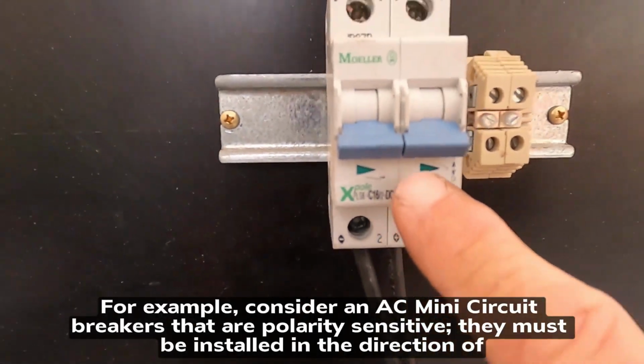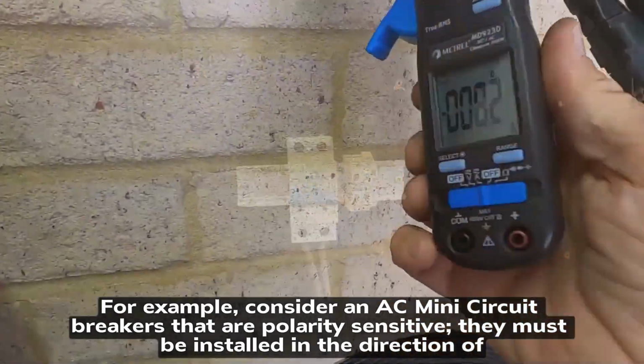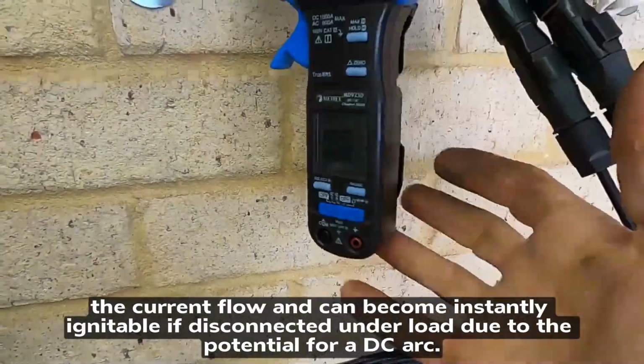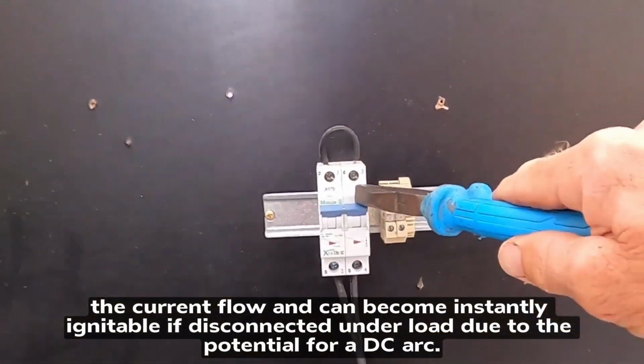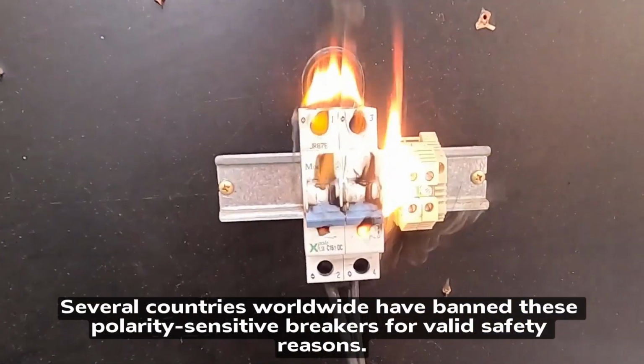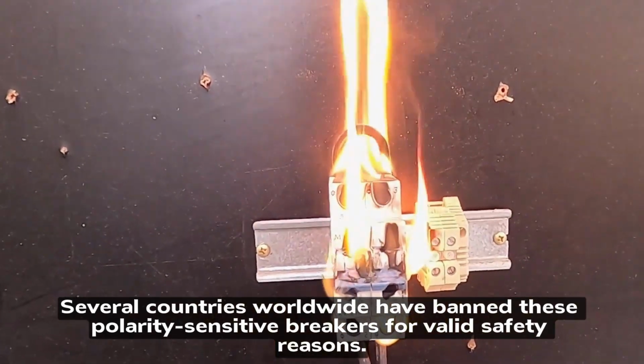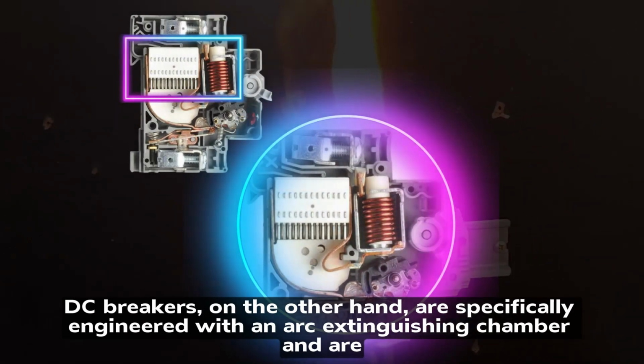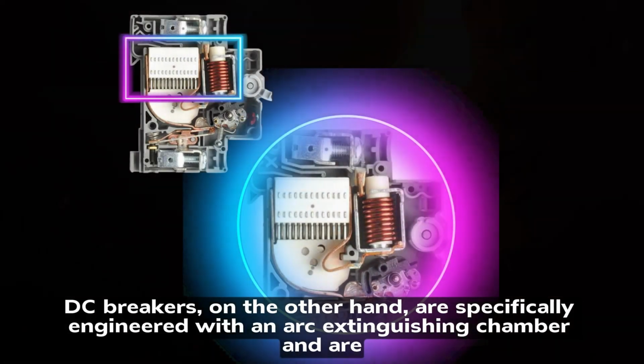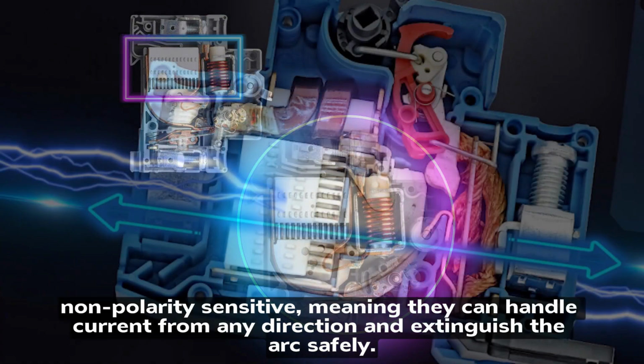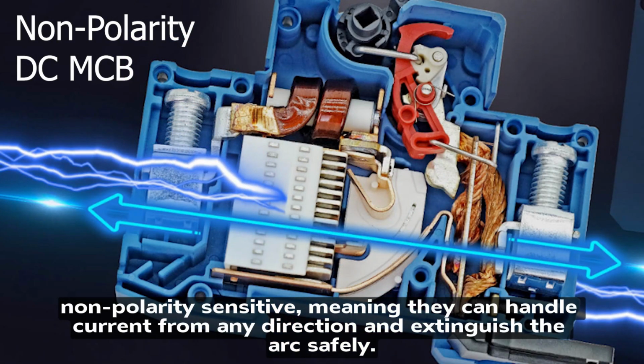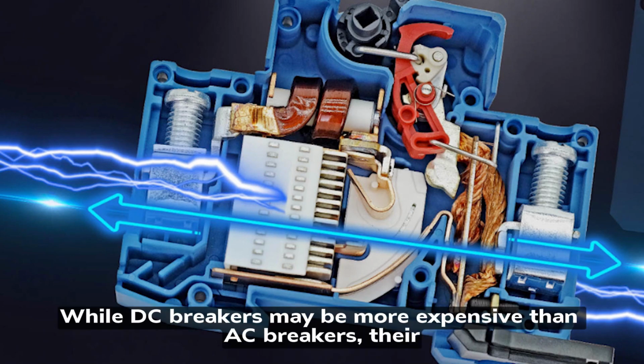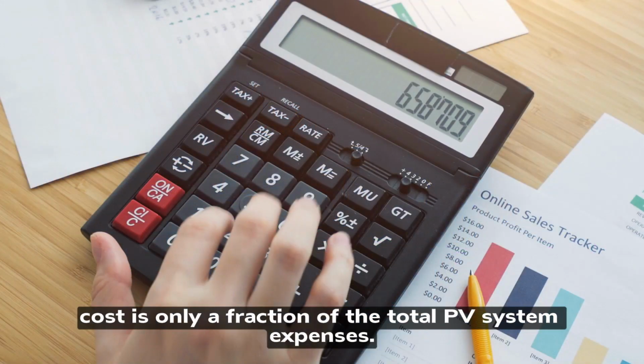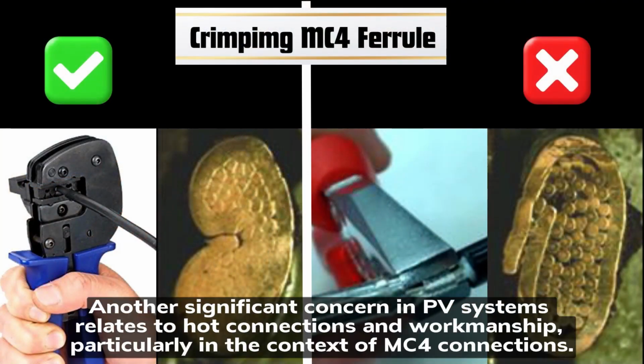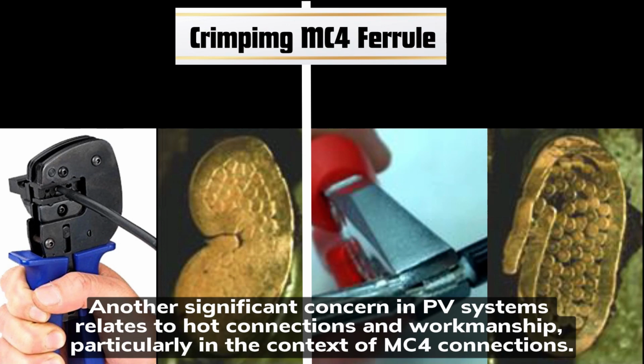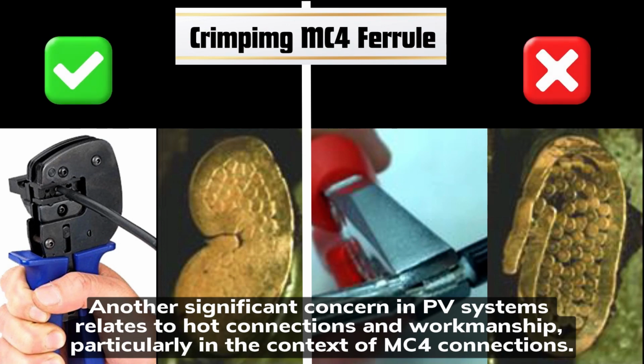For example, consider AC miniature circuit breakers that are polarity sensitive. They must be installed in the direction of the current flow and can become instantly ignitable if disconnected under load due to the potential for a DC arc. Several countries worldwide have banned these polarity-sensitive breakers for valid safety reasons. DC breakers, on the other hand, are specifically engineered with an arc-extinguishing chamber and are non-polarity sensitive, meaning they can handle current from any direction and extinguish the arc safely. While DC breakers may be more expensive than AC breakers, their cost is only a fraction of the total PV system expenses.